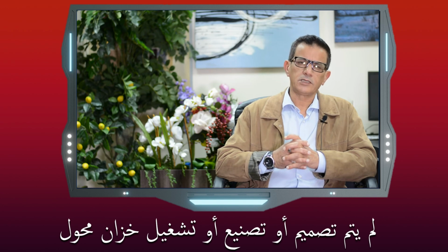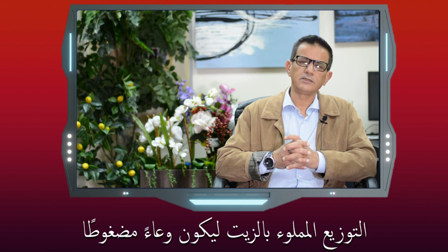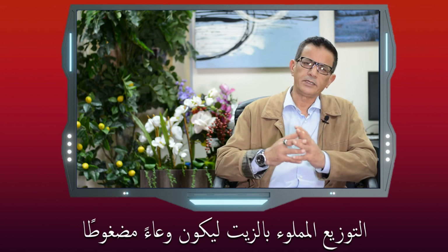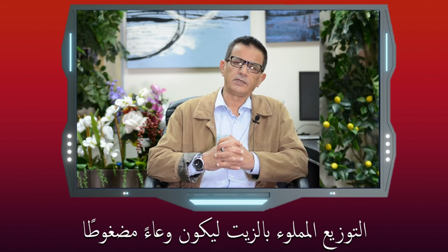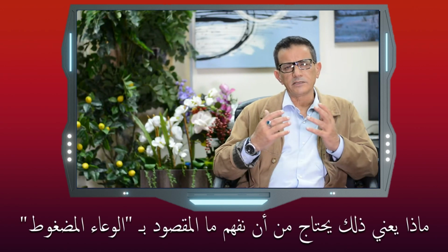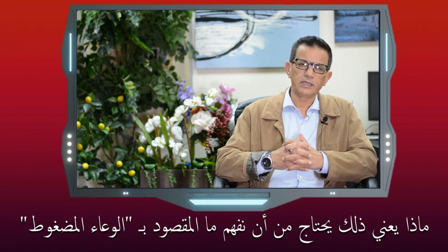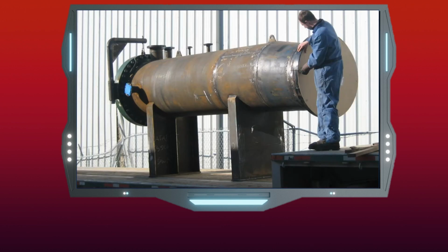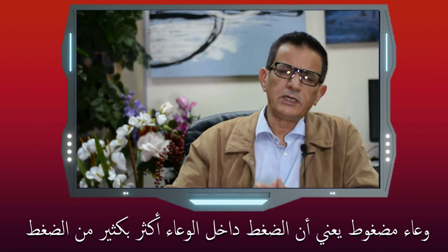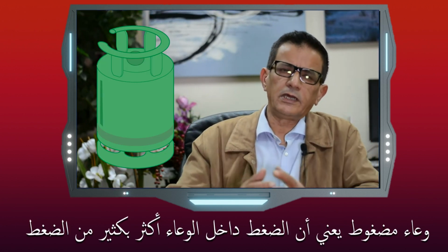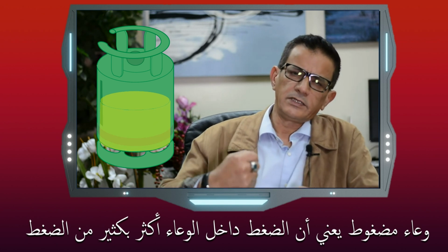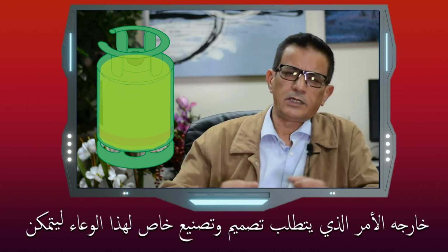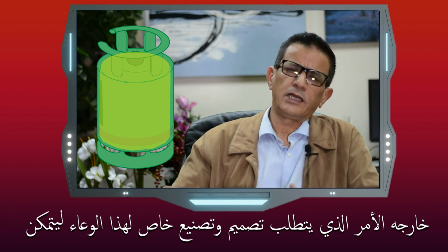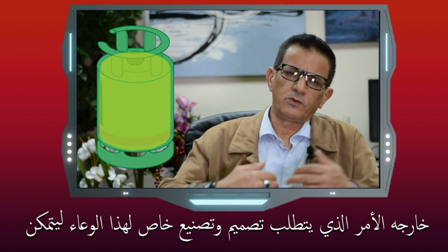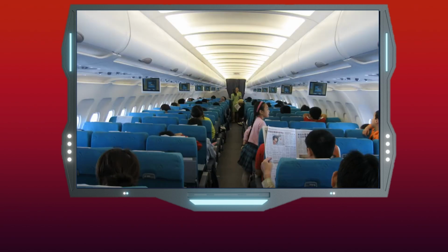Bismillah ar-Rahman ar-Rahim. The tank of an oil-filled distribution transformer is not designed or manufactured or operated to be a pressurized vessel. What does this mean? It needs us to understand what is meant by a pressurized vessel. A pressurized vessel means there is a container where the pressure inside the container is much more than the pressure outside it. So it will have special design and manufacturing to be able to withstand this difference in pressure.